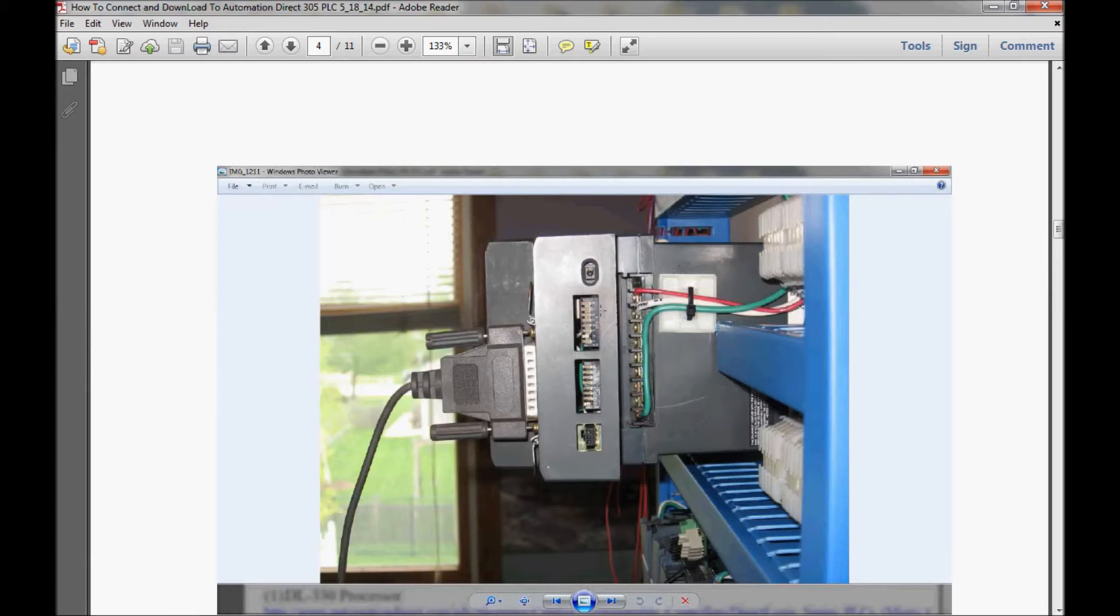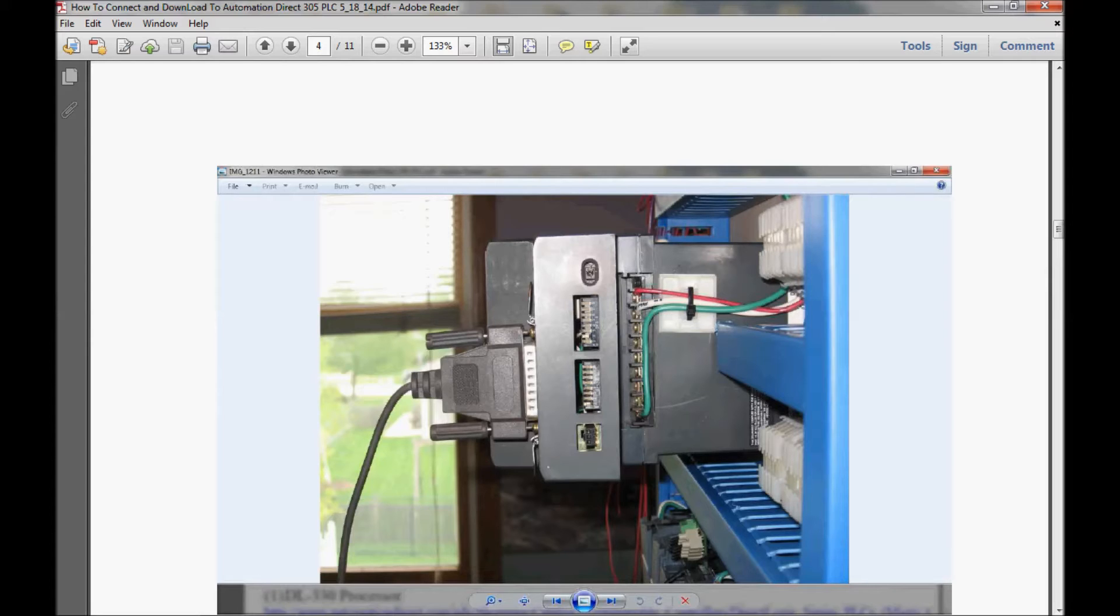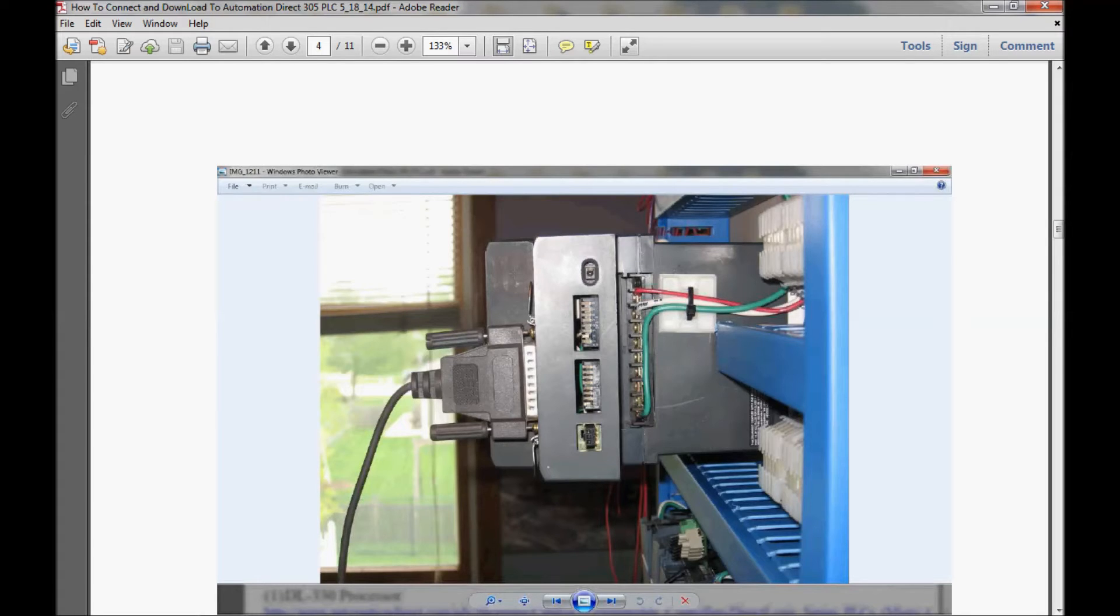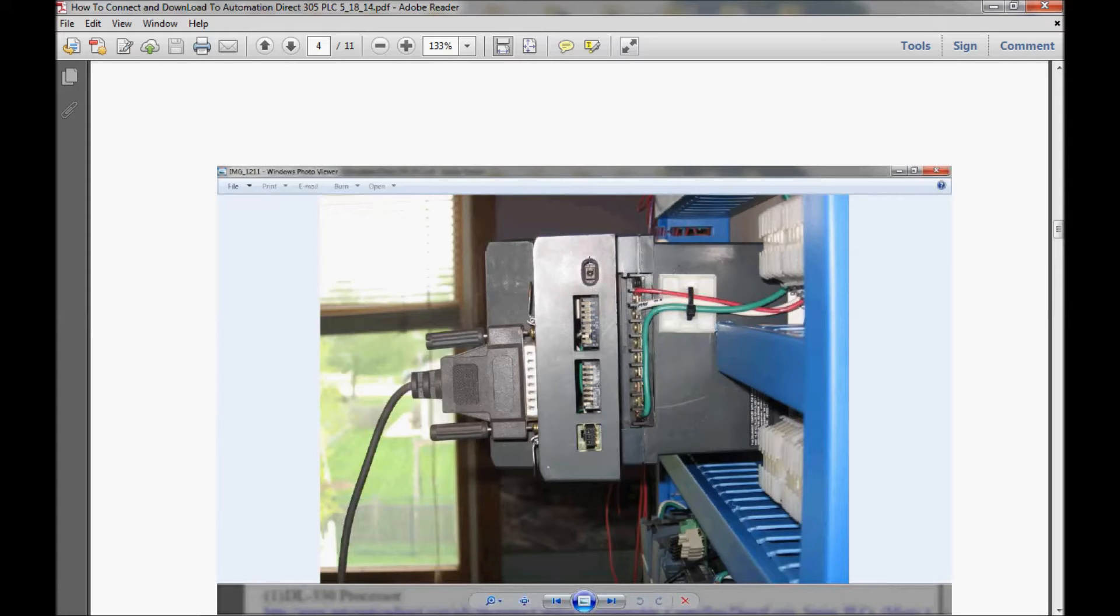Now here, up at the top, I have an online and offline switch. That is in the up mode, which selects the data communications unit to be online. In the offline mode, I can connect a handheld programmer, which I have on the data communications unit in this picture here on the front. That allows me to use the handheld programmer. Now if I'm going to be using my computer, I need to be in the online mode. So that switch needs to be up.